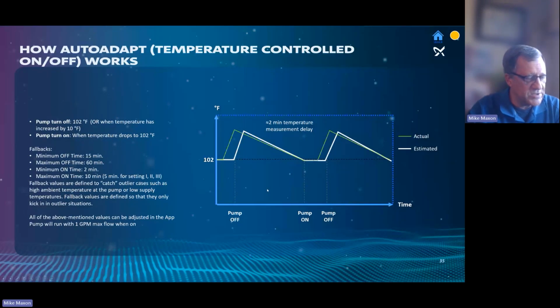So we know that since it's a temperature estimator, it's actually pretty good at getting the temperature right. It's just not really fast. So if we set it for 105 degrees, in reality, once it shuts off seeing 105 degrees, the water temperature is going to be a little bit higher than that, maybe 107 or 108.